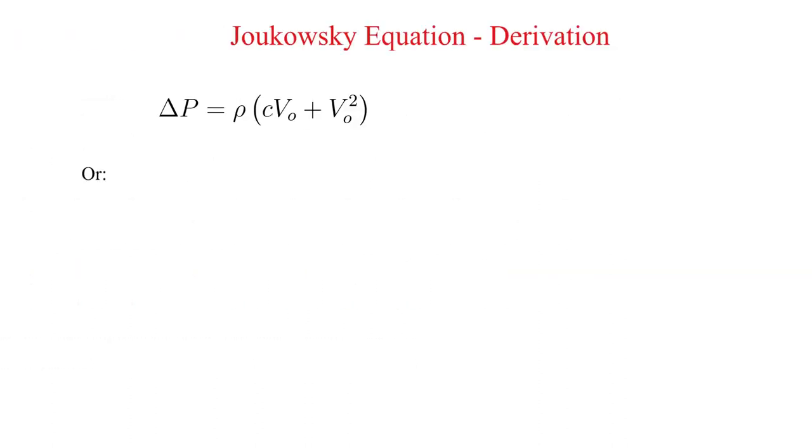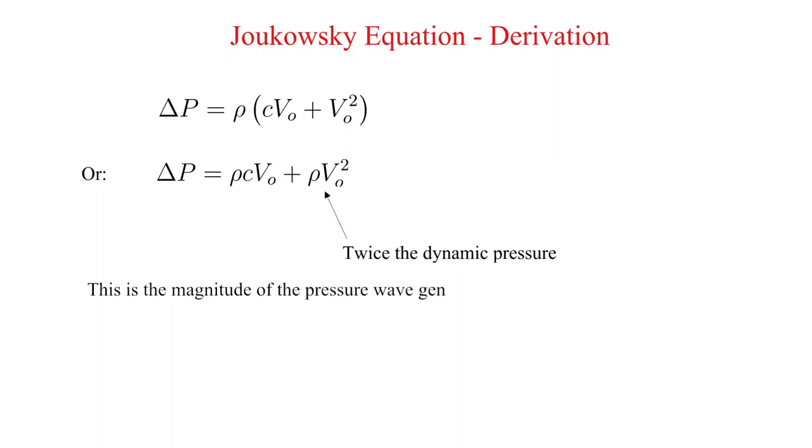Let's expand this equation. We get delta P is equal to rho times c times V0 plus rho times V0 squared. Notice that the second term is twice the dynamic pressure. This expression is the magnitude of the pressure wave generated following an instantaneous closure of a valve with an initial velocity of V0. However, this is not the Joukowsky equation.